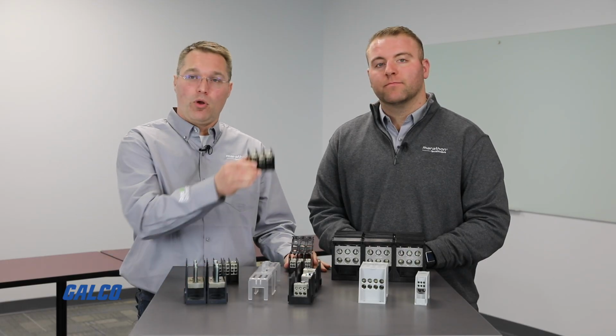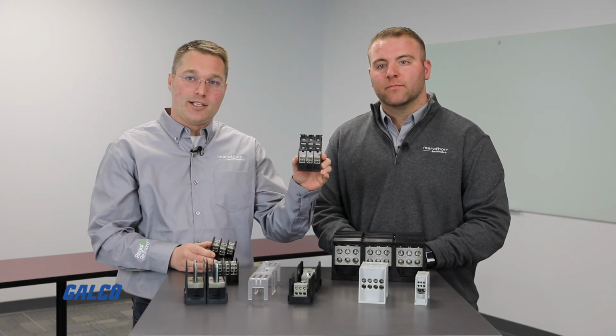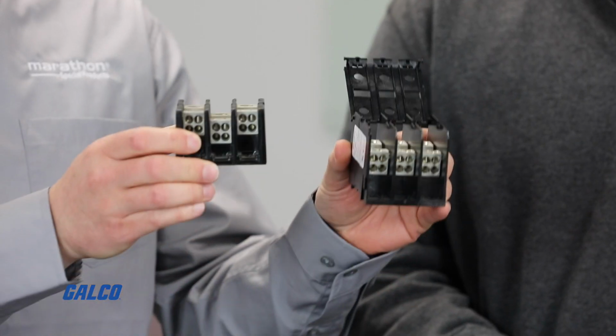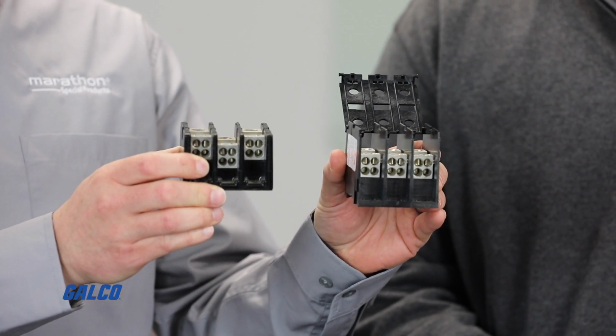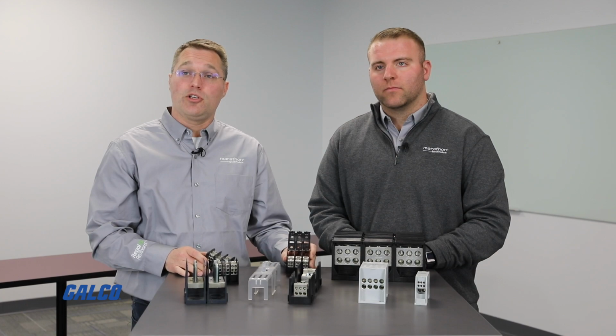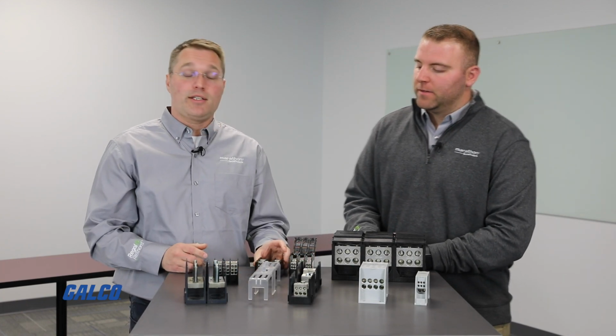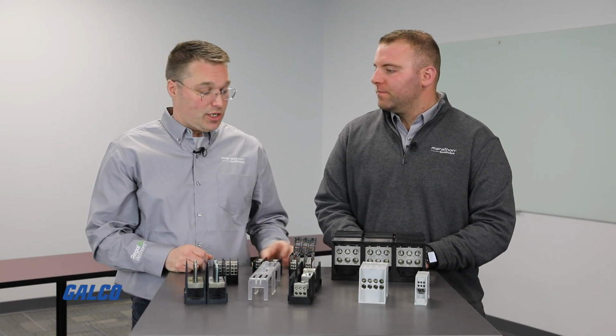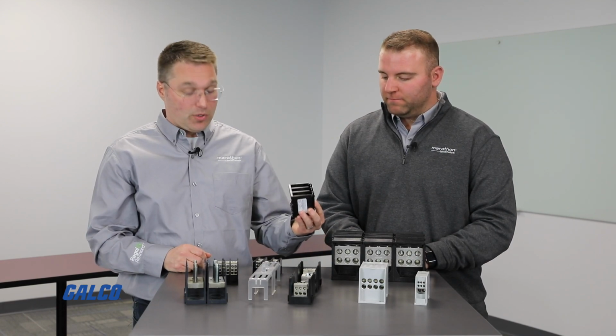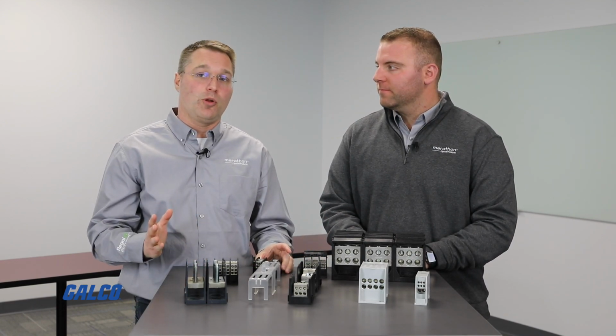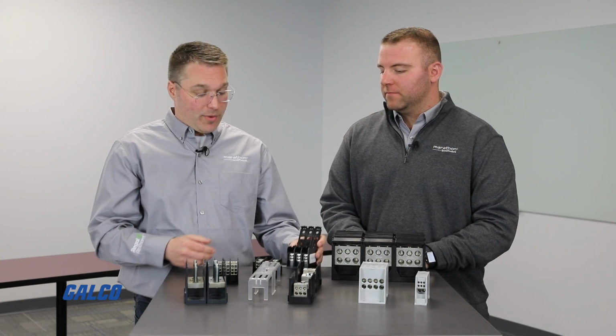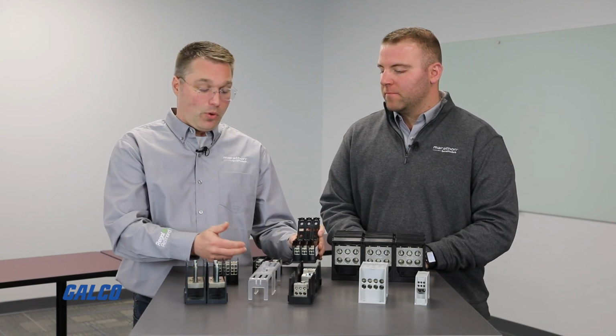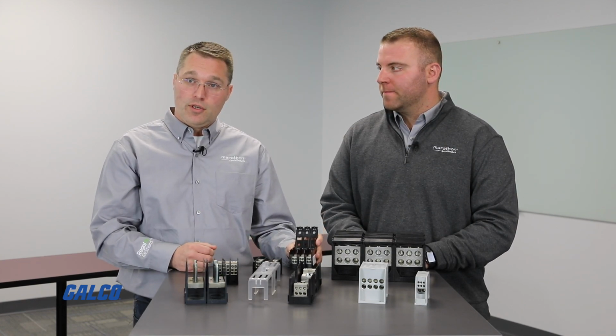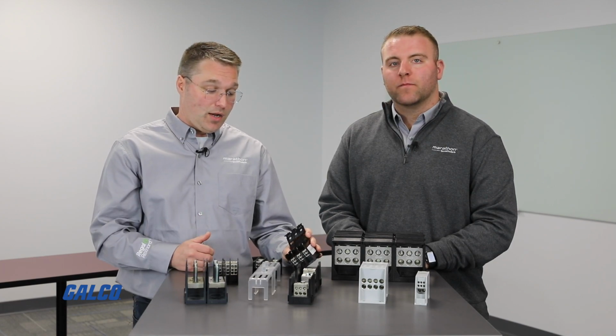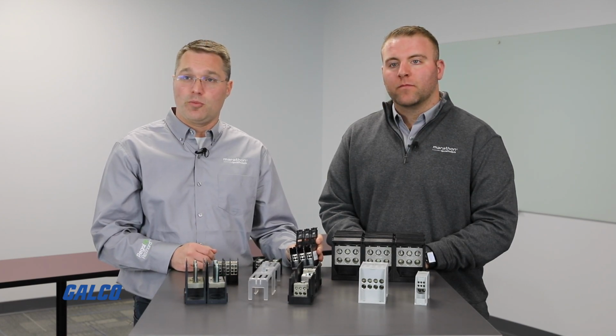One difference you'll see from an older phenolic product to the new thermoplastic one is that the barriers are much higher on these. This is because of UL agency compliance. About 10 years ago, UL created a specific standard for a power distribution block which differentiated it from a general terminal block. This requirement specified larger spacings from pole to pole and pole to ground than what was previously provided for a UL recognized terminal block.